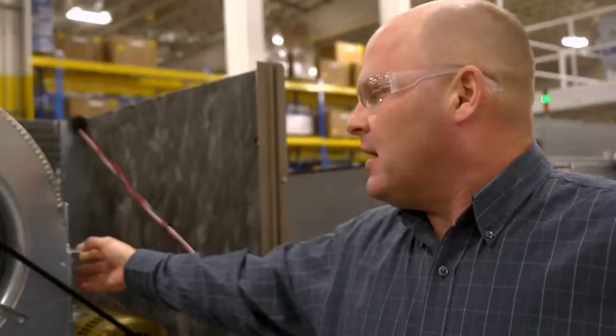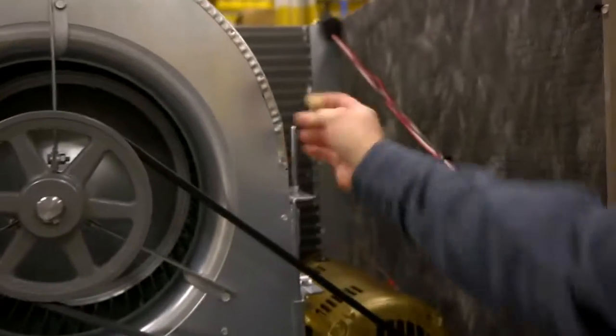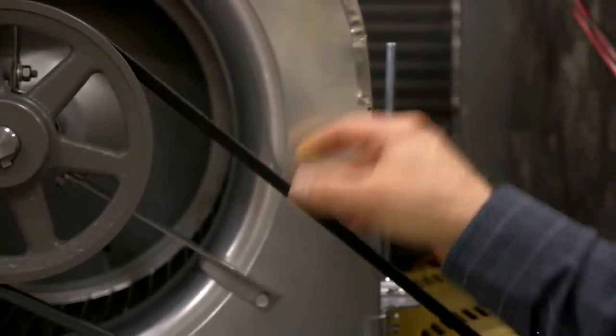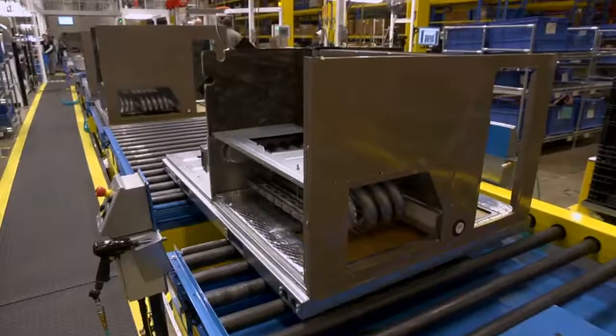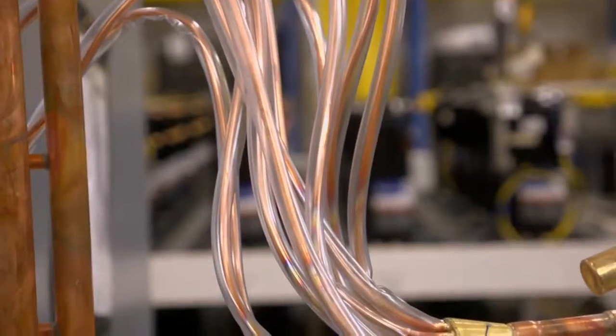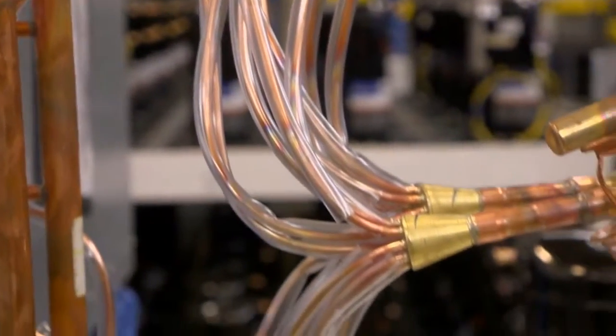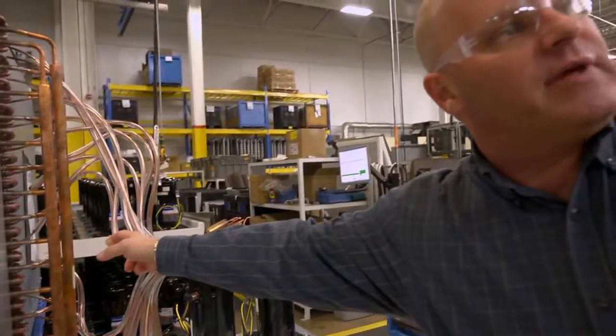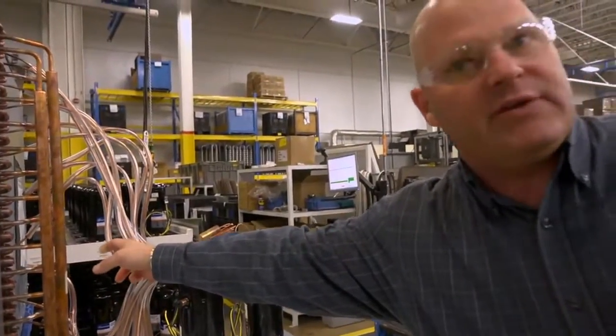The strength there is to keep the vibration and noise down to a minimum. We've actually put in an adjustable tension for the belt. We can actually get this to be perfect, which is what we call a 1/4 inch of deflection. So we do this on all of our product here. We use plastic sleeving on what we call the distributor tubes. If they weren't coated, they could rub together, and a lot of competition has that issue where they rub together.